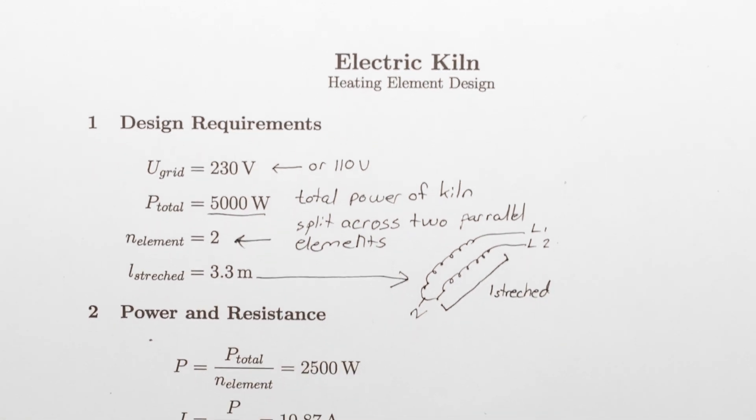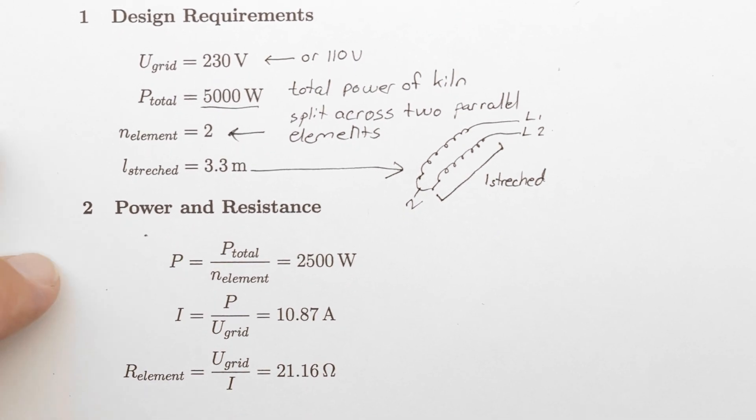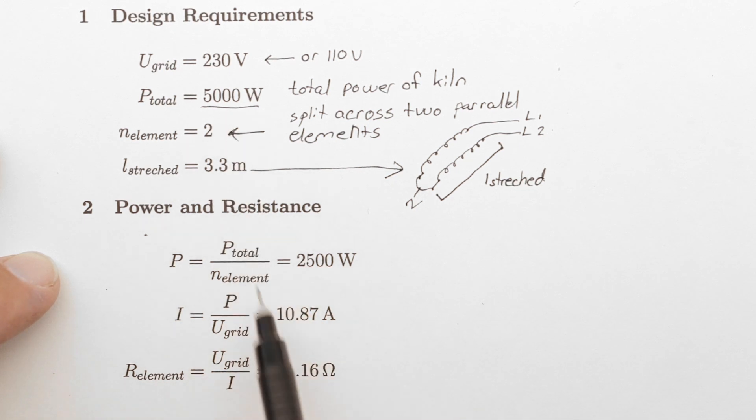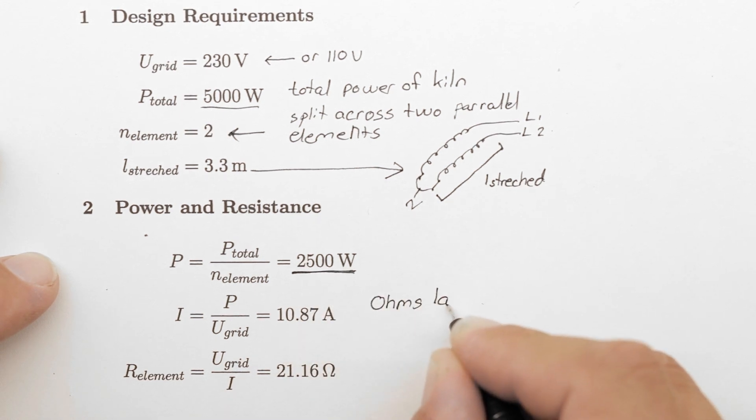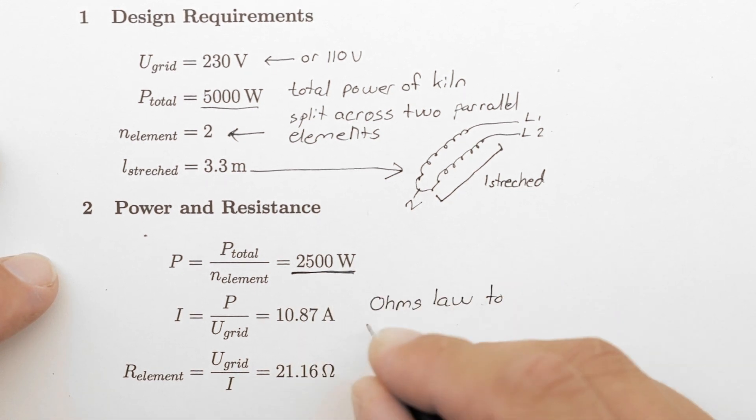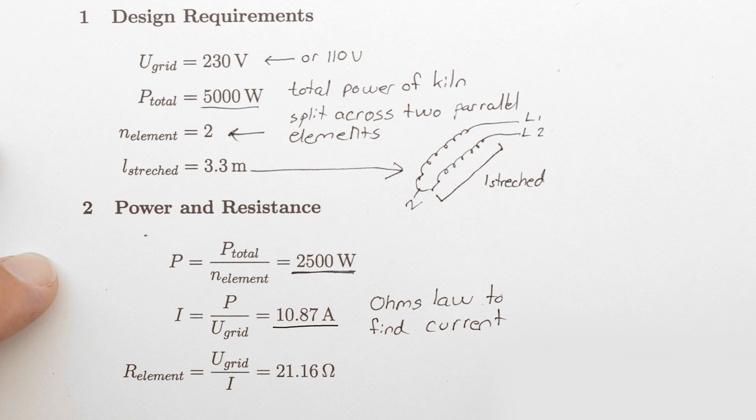Now we can determine the current and resistance required to obtain the desired total power level. The power of each element is simply the total power divided by the number of elements, giving us 2.5 kilowatts. Ohm's law can be applied to calculate the needed current to obtain 2.5 kilowatts when running at 230 volts. Just below 11 amps, which is easily provided by the 16 amp breakers in my current workshop.